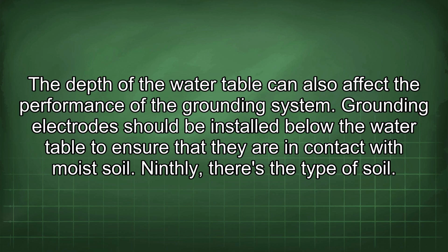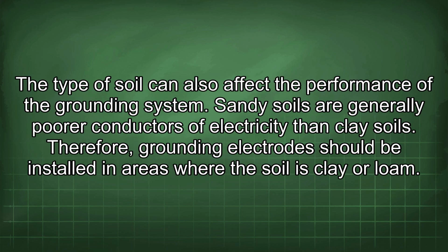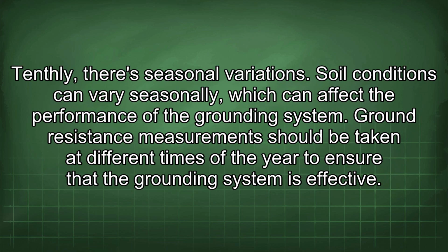Ninthly, there's the type of soil. The type of soil can also affect the performance of the grounding system. Sandy soils are generally poorer conductors of electricity than clay soils. Therefore, grounding electrodes should be installed in areas where the soil is clay or loam. Tenthly, there are seasonal variations. Soil conditions can vary seasonally, which can affect the performance of the grounding system. Ground resistance measurements should be taken at different times of the year to ensure that the grounding system is effective.